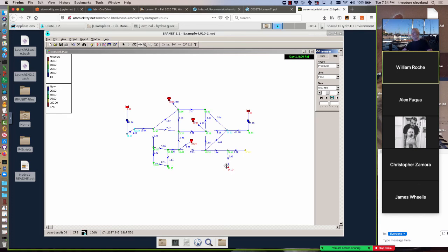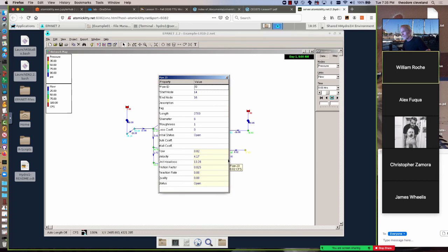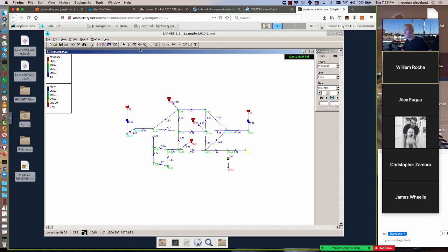But as we run the simulation, we look for red right there. We have a case at 9 hours into the simulation where the pressure at this node drops below our statutory requirement. And again, we'd use that information to help redesign or alleviate whatever that low pressure cause is. By far the easiest would be to make the pipe bigger. Just go up to an 8-inch pipe, rerun the simulation, choose the OK. Remember, at time number 9 is when bad stuff happens.